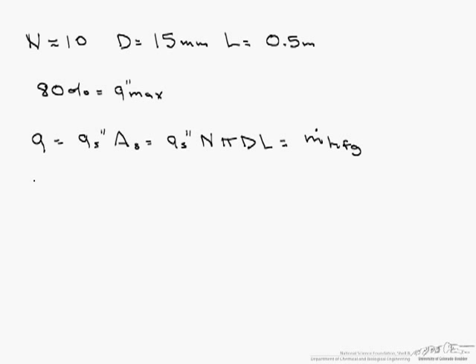So what we are looking for is this vapor production rate, or m dot, which is our heat flux times the number of tubes times pi dl divided by h_fg, or the heat of vaporization.